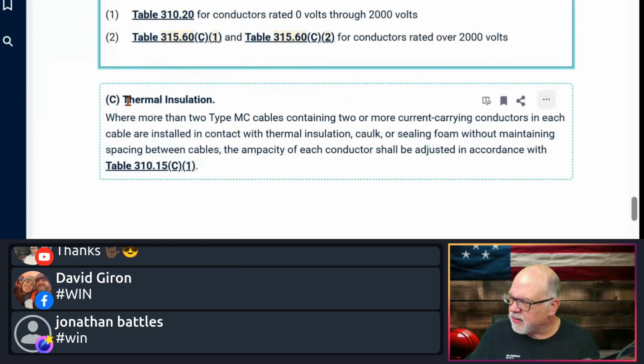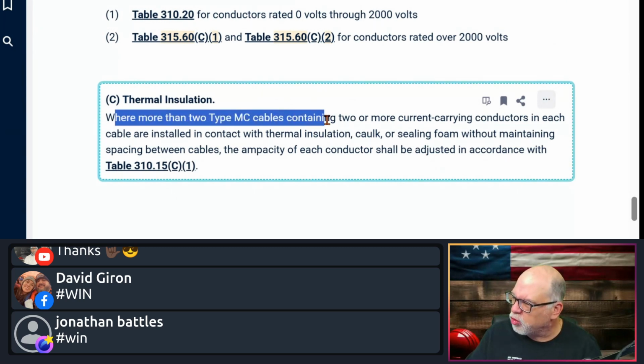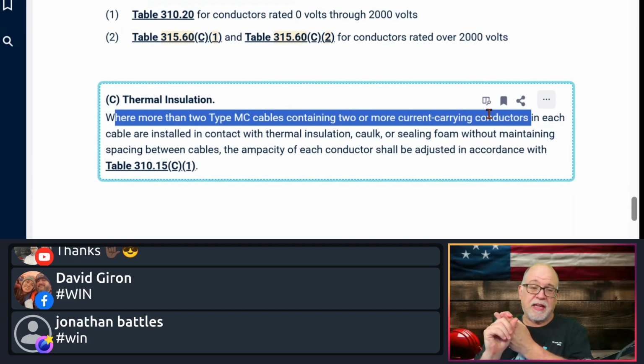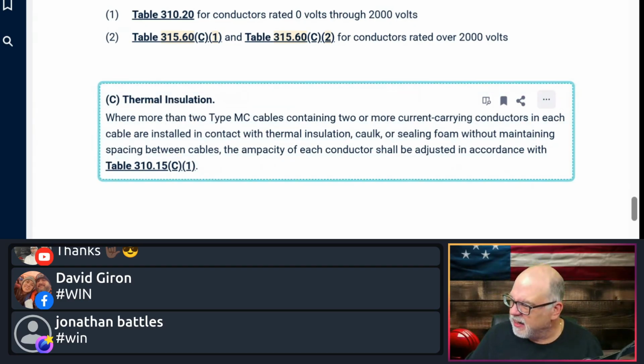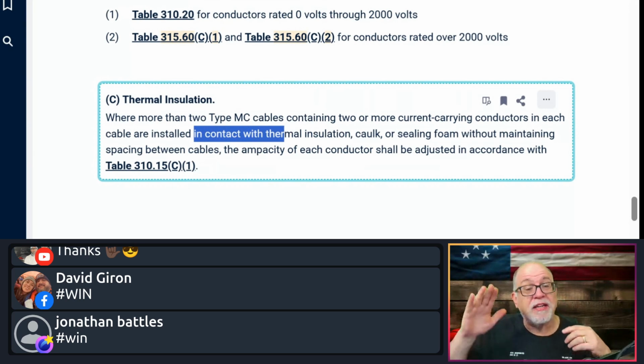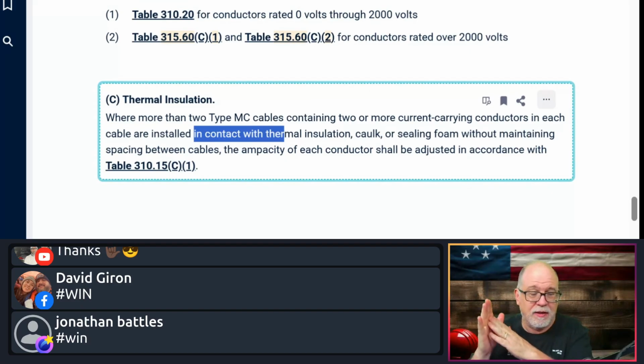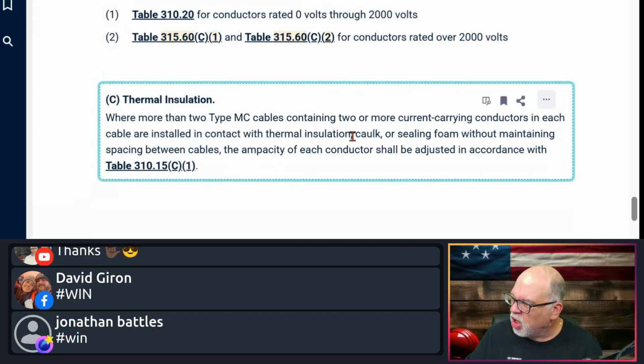Watch this one. Ready? It says where more than two type MC cables containing two or more current carrying conductors. And by the way, an MC cable with a 14/2 with an equipment ground, or a 12/2 with equipment ground, that is two current carrying conductors in that cable, the black and the white. Okay. So it says where you have more than two. So three or more, right? So where more than two MC cables that contain two or more current carrying conductors in each cable are installed in contact. All right, look, not through, not on top. It says in contact with it. So if it's touching it, okay, it says are installed in contact with thermal insulation, caulk, or sealing foam without maintaining spacing between the cables. It says the ampacity of each conductor shall be adjusted in accordance with 310.15(C)(1).